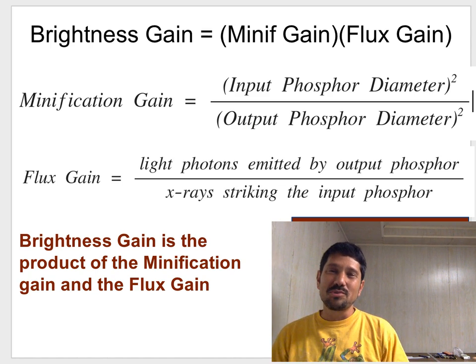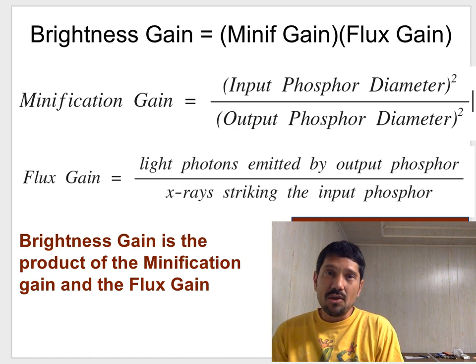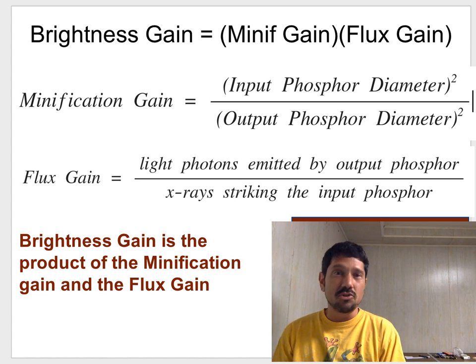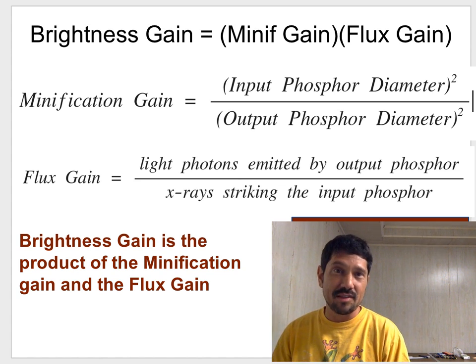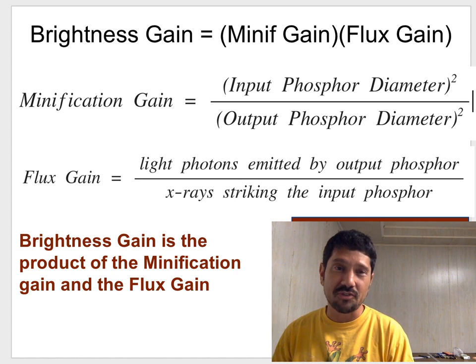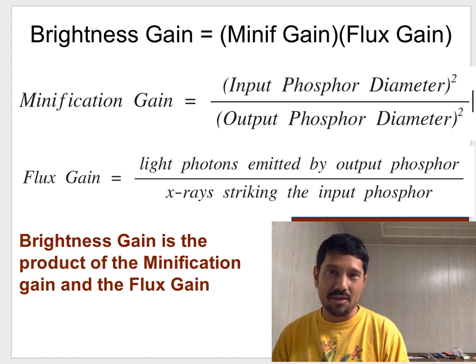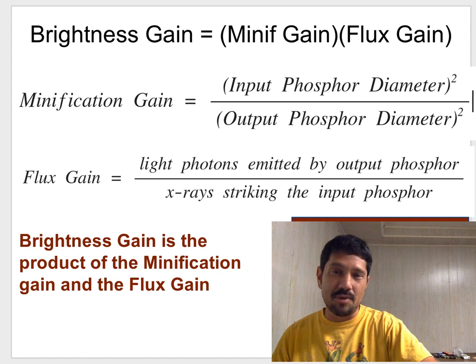But wait! But wait! There's more! Okay. So, what we do is we have an overall brightness gain, which is the product of the minification gain times the flux gain. What did I gain due to minifying my image and having those geometries? What do I get by picking these cool phosphors and this great photocathode so I can crank up my signal? So the brightness gain is the product of the two.